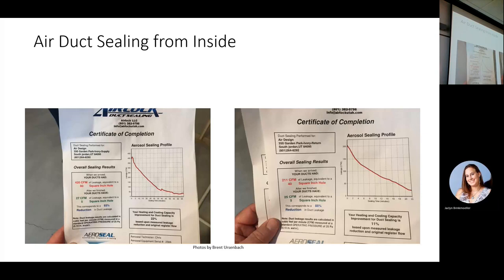Lots of leaks in duct systems are at the furnace, where the return or air filter cabinet hooks onto it, where a coil cabinet goes on top of the furnace, where the plenum flange mates on top of the coil cabinet or the furnace. And why don't we put down a bead of sealer on those mating surfaces as we're putting them together? Rather, we try to smear the crap around the outside of it and hope it holds. It's kind of beyond me. It's kind of like a plumber trying to seal a leak in his ABS. He fills it up with water and it's leaking, and you might have seen him try to smear glue on it from the outside to shove it in the little leak. And then after he works at it for a while, he gets mad when he cuts the fitting out and glues a new fitting in, because you don't seal well from outside. What I'm trying to say is, for HVAC people, you're going to have a lot tighter duct systems if you put sealer down as you're putting it together. It's going to work much, much better.